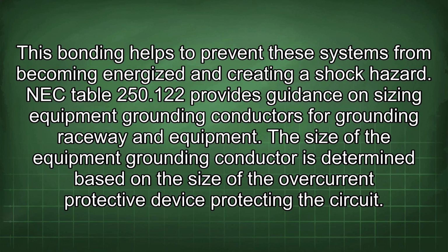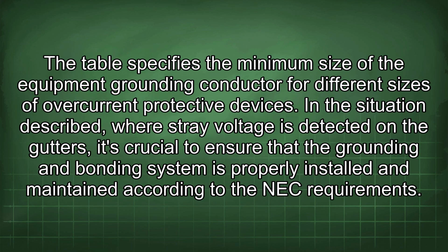NEC Table 250.122 provides guidance on sizing equipment grounding conductors for grounding raceway and equipment. The size of the equipment grounding conductor is determined based on the size of the overcurrent protective device protecting the circuit. The table specifies the minimum size of the equipment grounding conductor for different sizes of overcurrent protective devices.